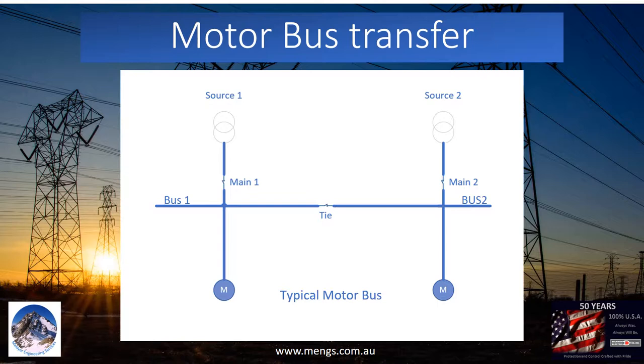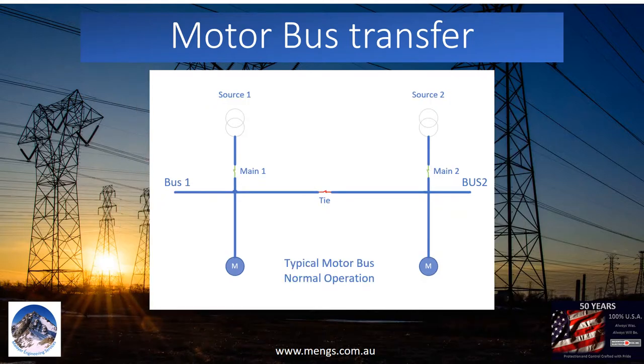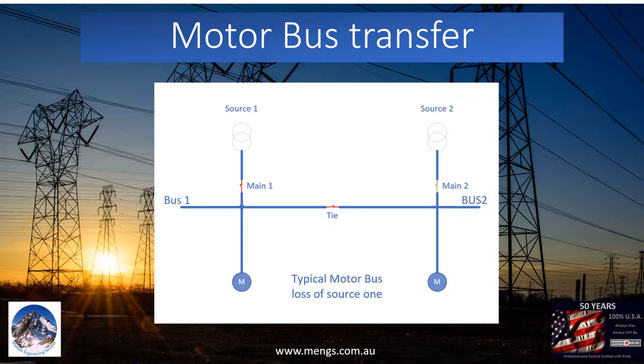For example, source 1 is the main source of supply for bus 1 and the redundant source of supply for bus 2. In normal operations, source 1 supplies bus 1 and source 2 supplies bus 2. If source 1 becomes unavailable, bus 1 will remain unsupplied. In this case, the only way to supply bus 1 is by closing the tie breaker and transferring bus 1's source of supply to source 2.